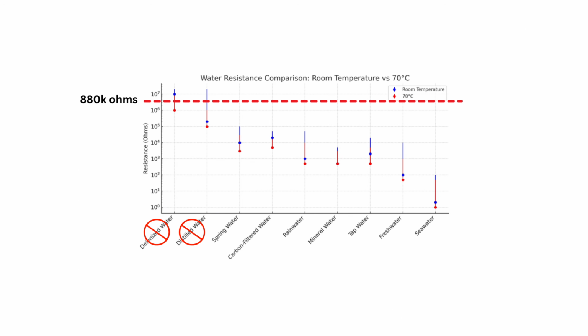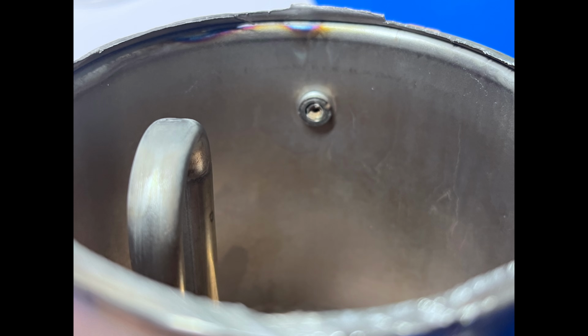However, even with filtered water you're going to need to descale eventually, and this is because this will happen. The biggest reason to descale in my opinion is to prevent the steam boiler inlet port from becoming blocked like this one, as this can eventually lead to the same very expensive repair as the failed descale could.